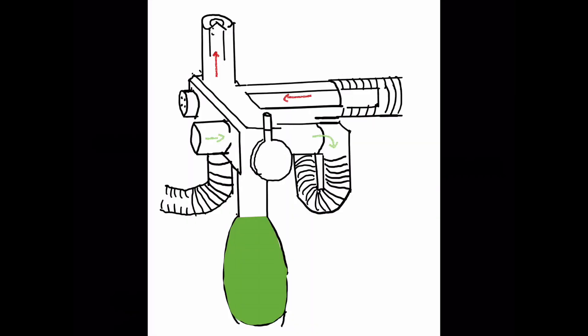On expiration, the expired gas travels through the expiratory tubing. Scavenging can be connected to the expiratory port, which reduces volatile waste to the atmosphere, meaning less exposure to members of staff in the theatre complex and less pollution.